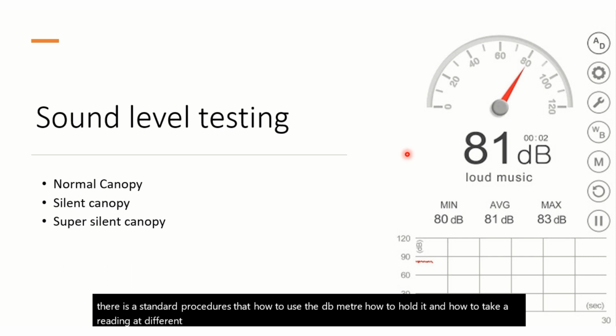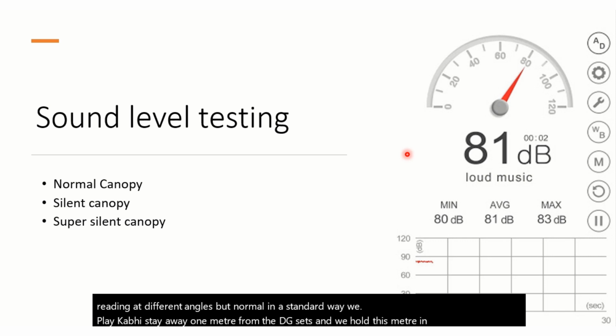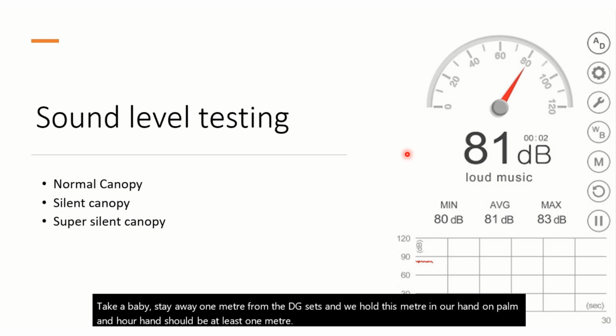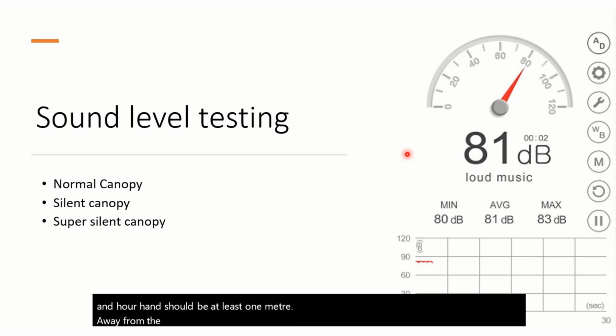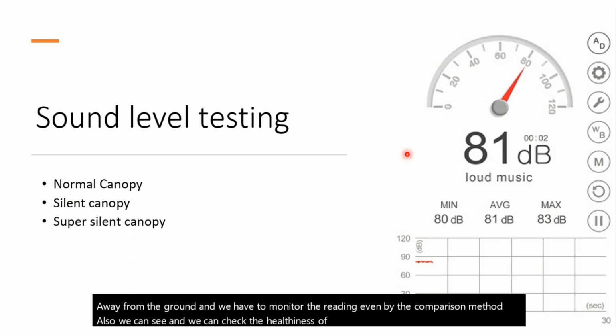But normally, in a standard way, we stay 1 meter away from the DG set, and we hold the meter in our palm, and our hand should be at least 1 meter above the ground, and we have to monitor the reading. Even by the comparison method we can check the healthiness of all the rotating equipment through this noise testing.